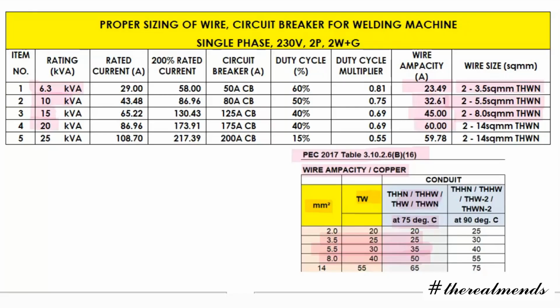So from the PEC again, 65 amperes at 75 degrees Celsius. So the wire is 14 square mm. Okay, and then for the last, 25 KVA, we have 59.78 amperes. So it still fits the 14 square mm, which has an ampacity of 65 amperes. Okay, so that's it, that's how easy it is to get the proper sizing of wire and the OCPD for our welding machines.